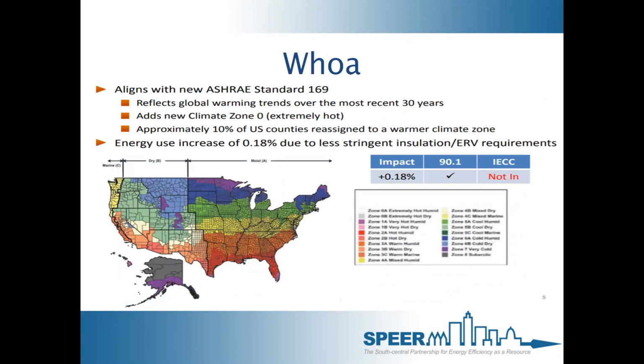Now this to me is the most significant change in ASHRAE 90.1 2016, and it's the new climate zone map. ASHRAE is saying now, hey, we're going to align the climate zone map with ASHRAE standard 169. And typically in years past, the IECC climate zone map has always aligned with the ASHRAE 90.1 climate zone map. Well, that's no longer the case in 90.1 2016 and the 2018 IECC.